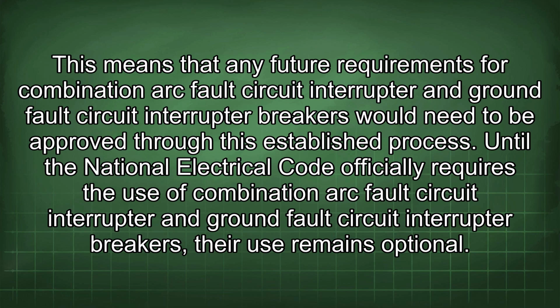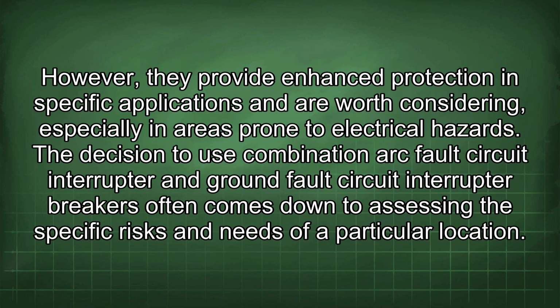Until the National Electrical Code officially requires the use of combination arc fault circuit interrupter and ground fault circuit interrupter breakers, their use remains optional. However, they provide enhanced protection in specific applications and are worth considering, especially in areas prone to electrical hazards. The decision to use combination arc fault circuit interrupter and ground fault circuit interrupter breakers often comes down to assessing the specific risks and needs of a particular location.